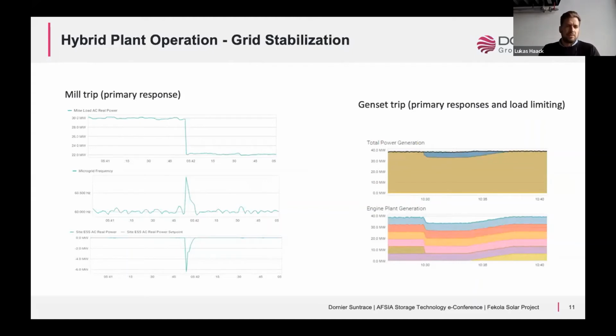Now, in order to keep the frequency stable, the battery needs to absorb power from the solar plant, shown on the bottom graph, because the solar plant inverters aren't able to ramp down in such a short time. The battery really enables keeping the frequency within the required bandwidth and keeps the system stable.